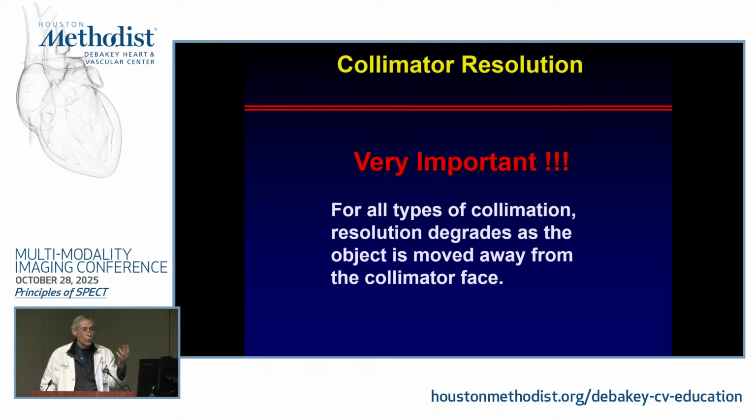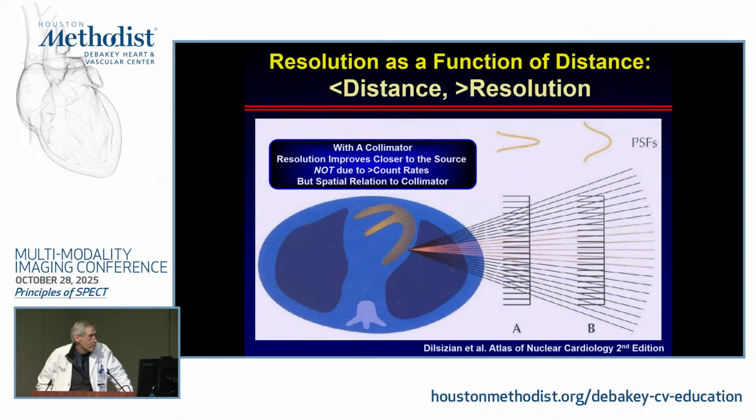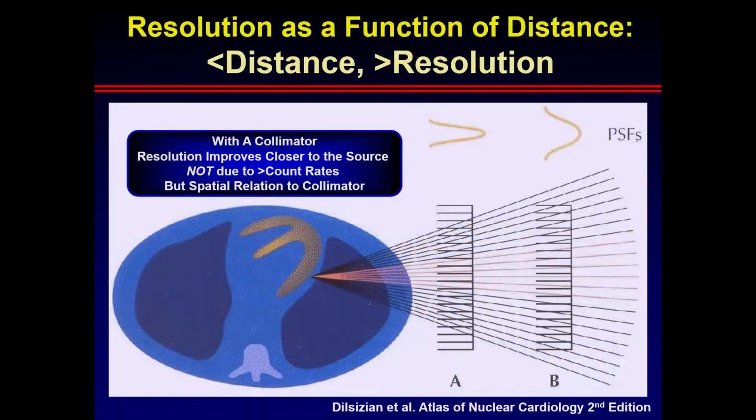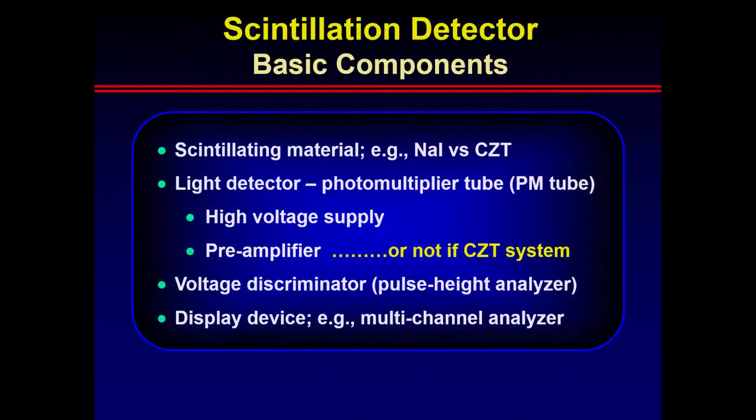So you have differential loss of resolution just based on the patient itself, irrespective of where the camera head is actually placed on the chest. And you can see that here in terms of spatial resolution, that as that camera collimator goes further away from the body, the point spread function becomes extremely wide and your spatial resolution degrades tremendously.